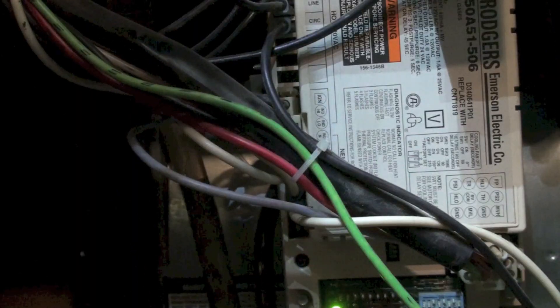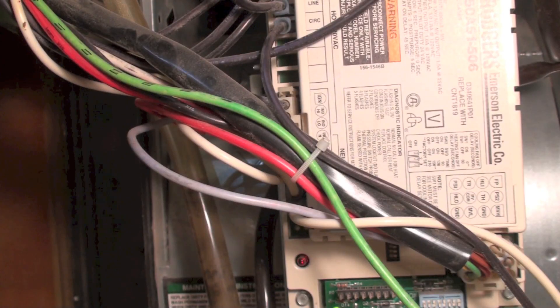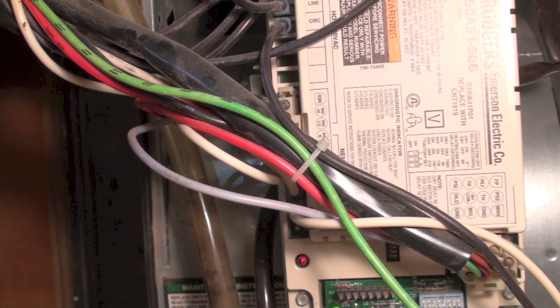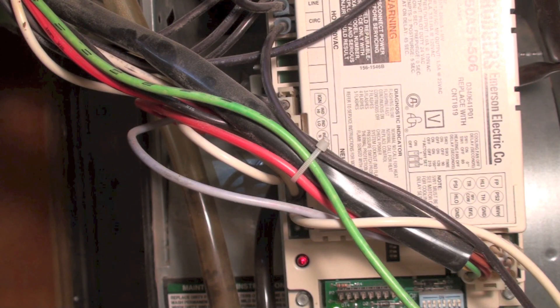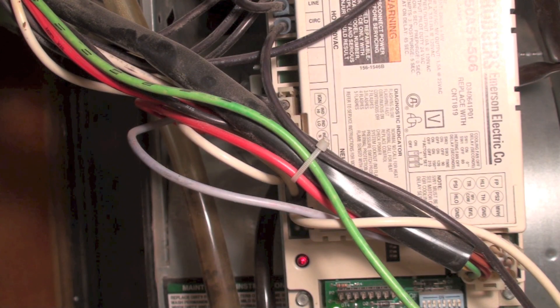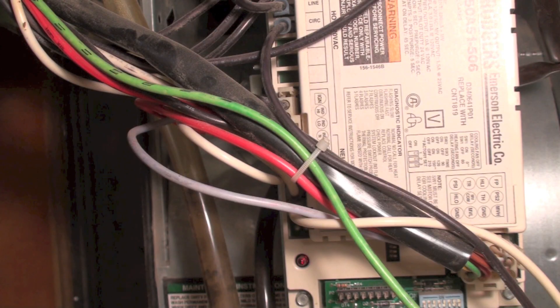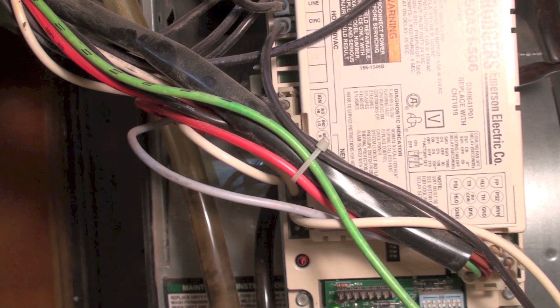Okay, the continuous on, that happens to be that way, the control has failed. There's also the flame sense with the gas valve off. Pretty uncommon, that'd be a stuck on gas valve. I haven't seen that one happen.